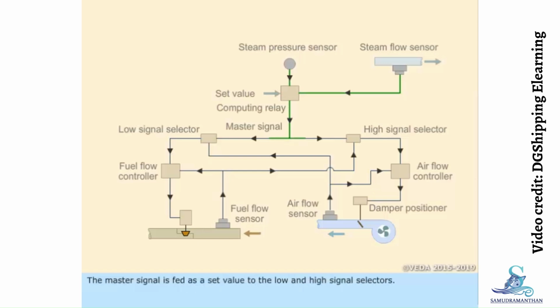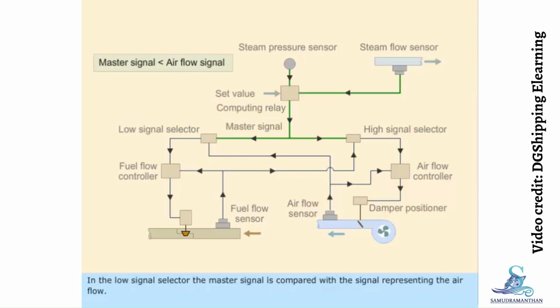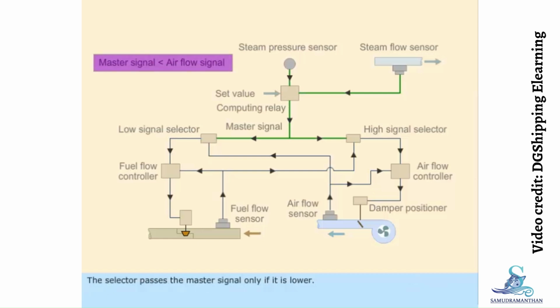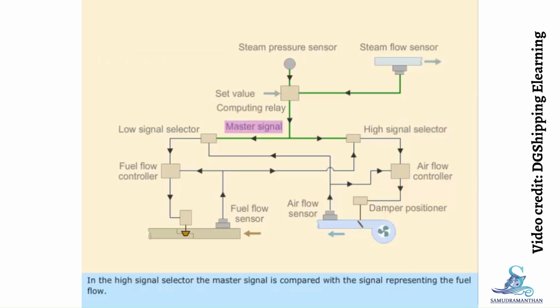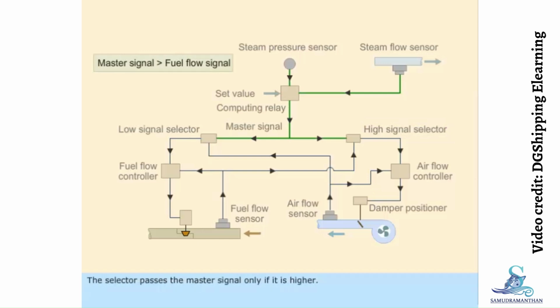The master signal is fed as a set value to the low and high signal selectors. In the low signal selector, the master signal is compared with the signal representing the airflow. The selector passes the master signal only if it is lower. In the high signal selector, the master signal is compared with the signal representing the fuel flow. The selector passes the master signal only if it is higher. When the steam demand is high, high signal selector passes the master signal to airflow controller.